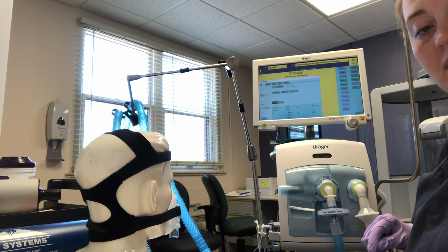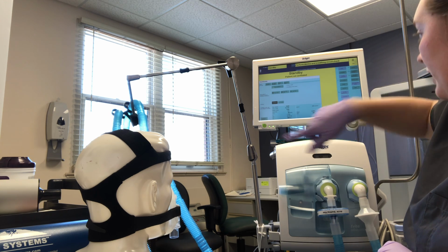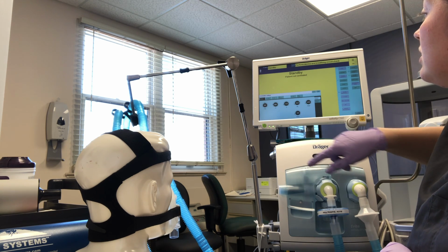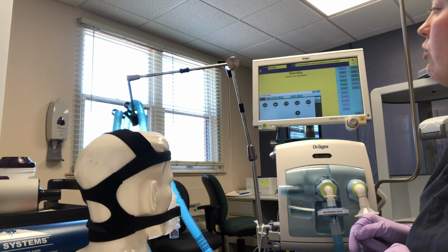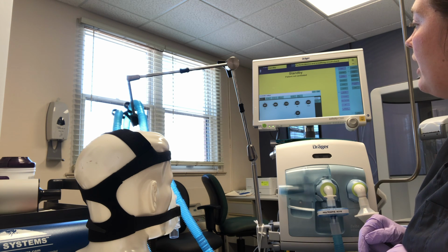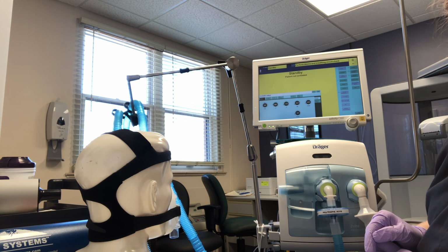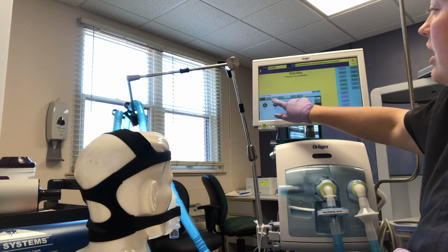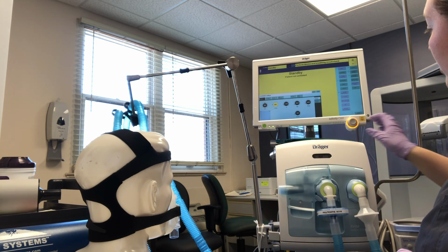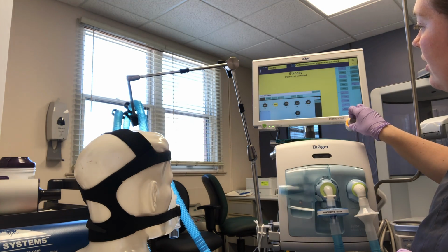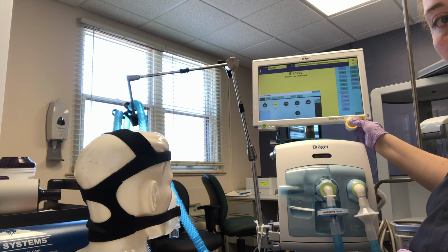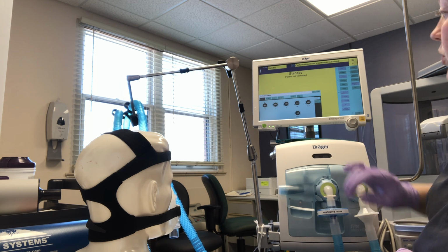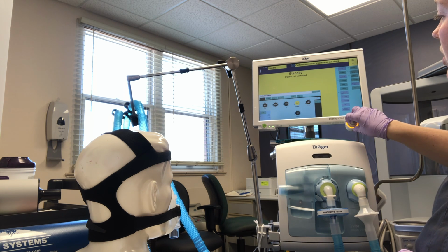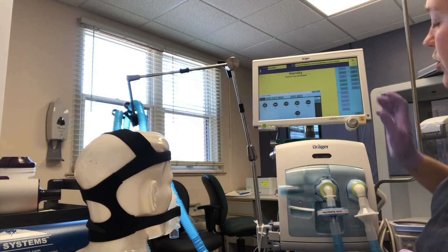So to do that, we want to be in volume control. So we're going to go to ventilation settings, and we're going to choose volume control, and we're going to set our settings. So the first setting we need to have is tidal volume. So we're just going to click the tidal volume, and we're going to dial it back to 500. And then once we're where we need to be, we just push the button to enter. We want our respiratory rate set at 16. So again, push 16 and push to enter.